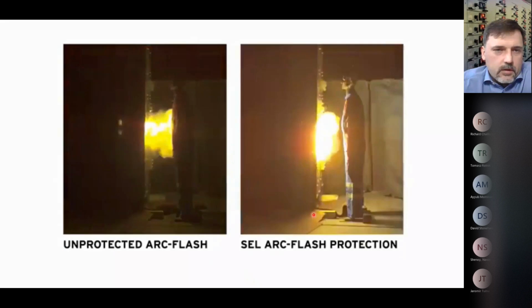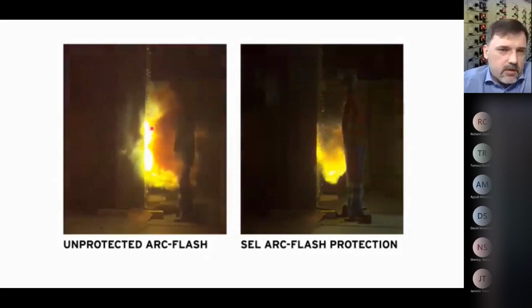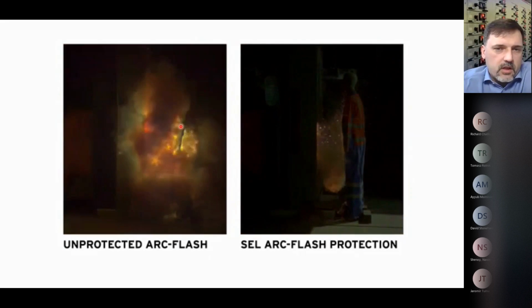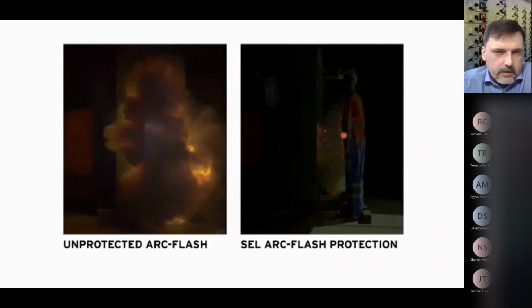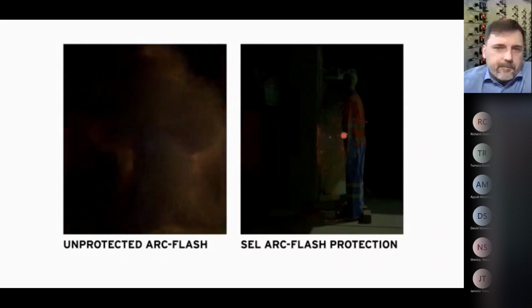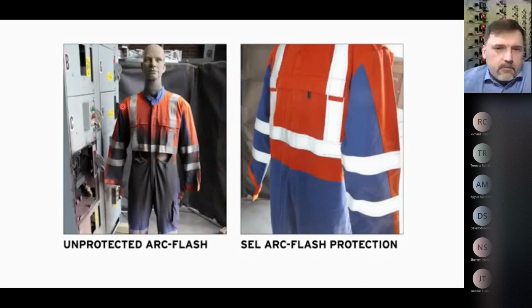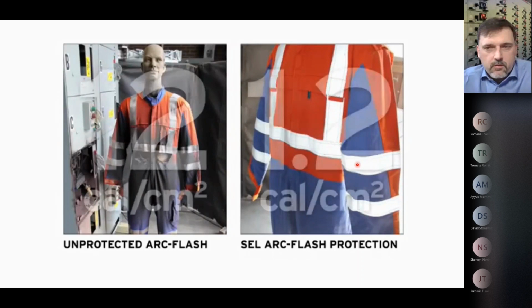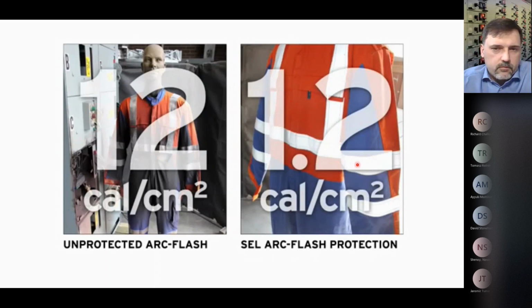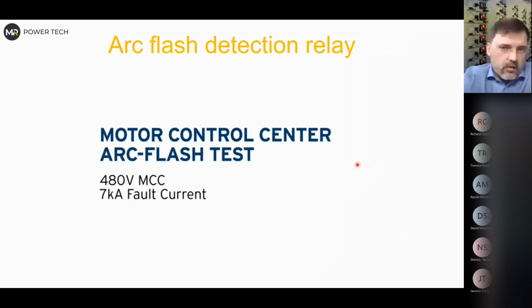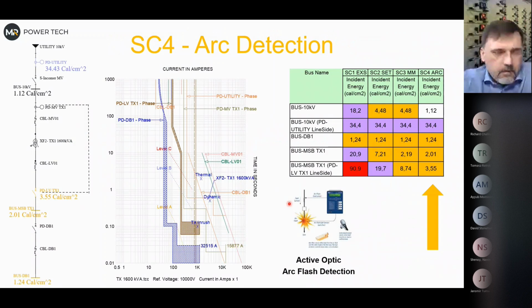Yeah, I hope you can see it step by step. So you see the pulsing when it's 500 milliseconds instead of 50 milliseconds. And that's why we use it. So we try to make our time much shorter. And when we use the arc flash detection system, it's a separate system, so we still can maintain the selectivity.